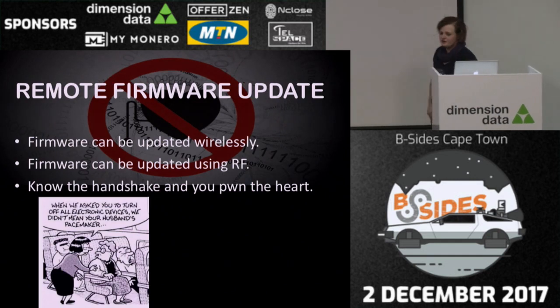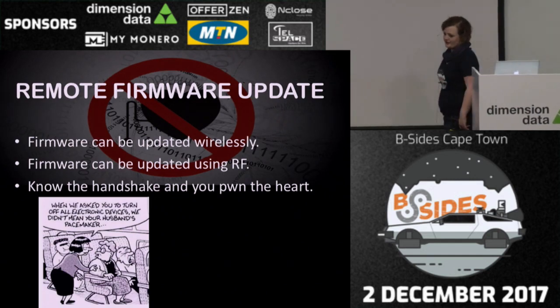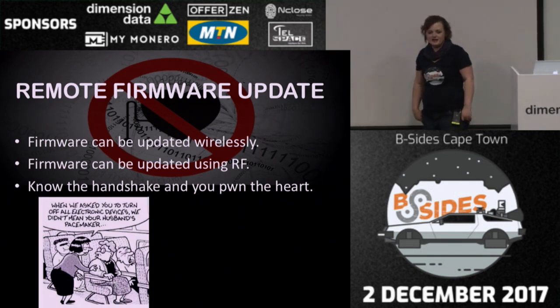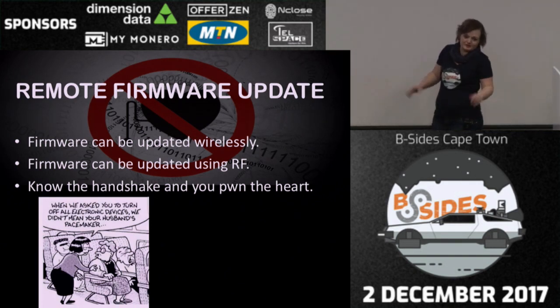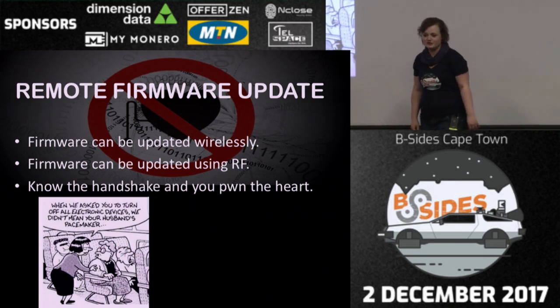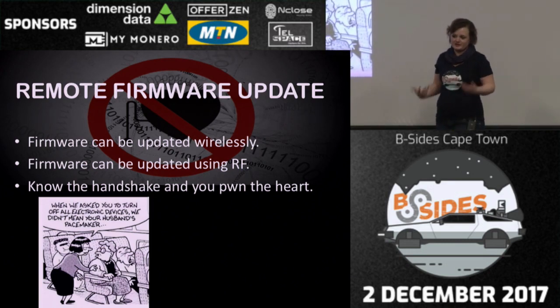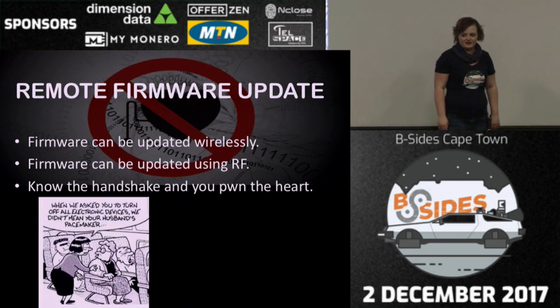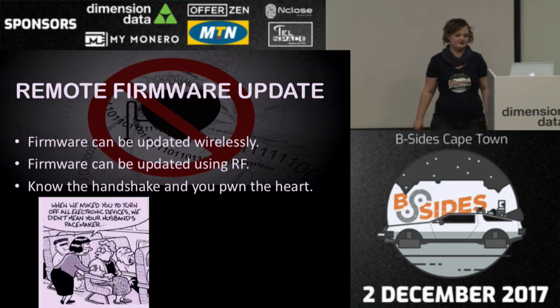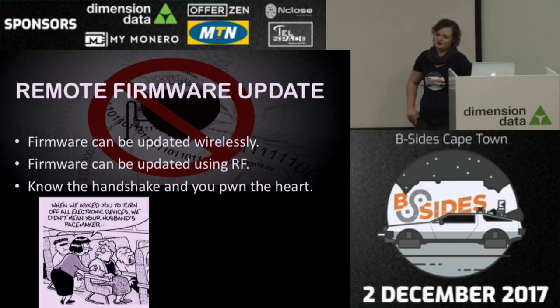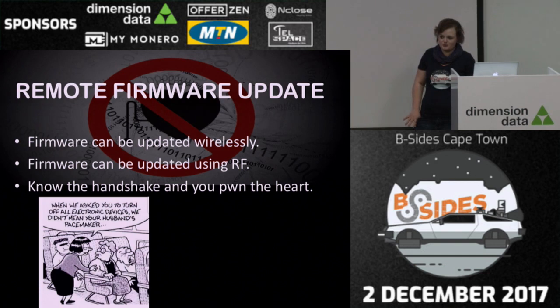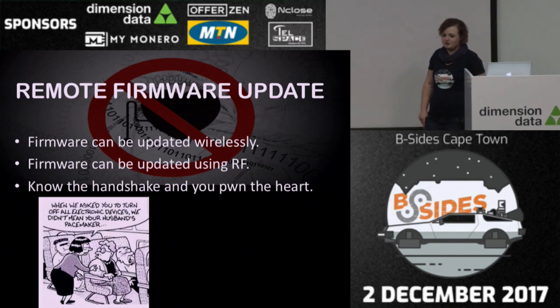So the firmware is not signed, which is generally a bad idea. Meaning, if I write something that looks like firmware and matches where it's supposed to go, this device is going to open up and accept it. And it gets better. If you know how to do the handshake, there's no specific memory that it's written into, or protected storage. It will just accept it.